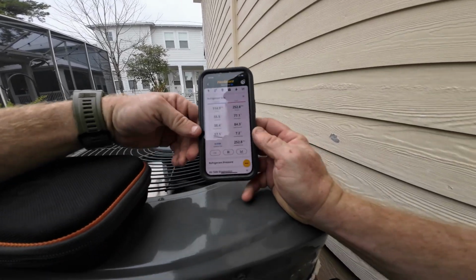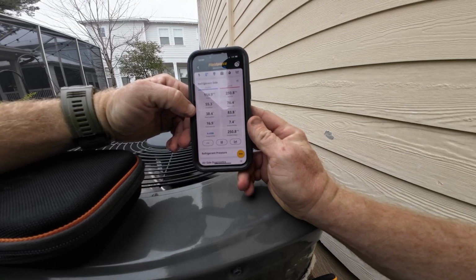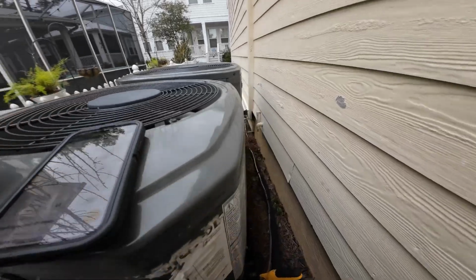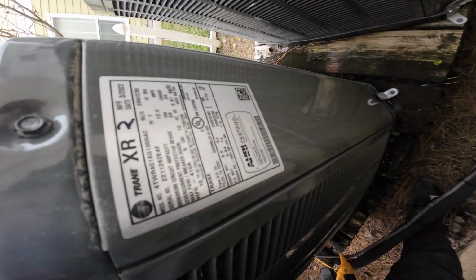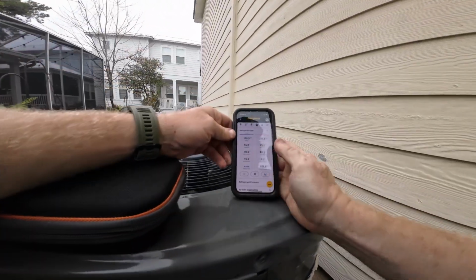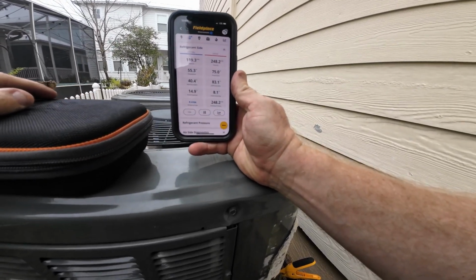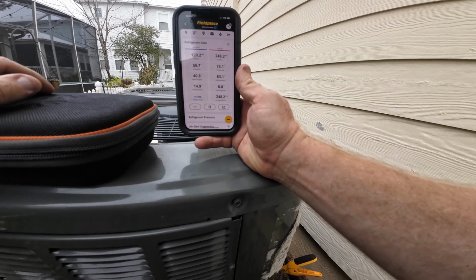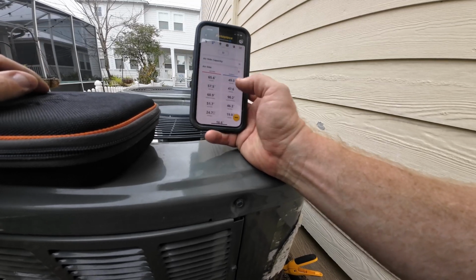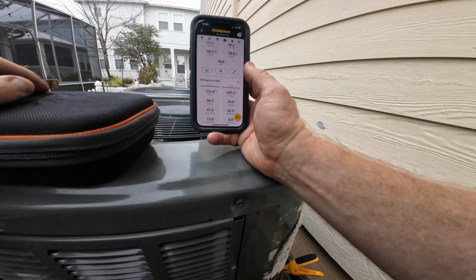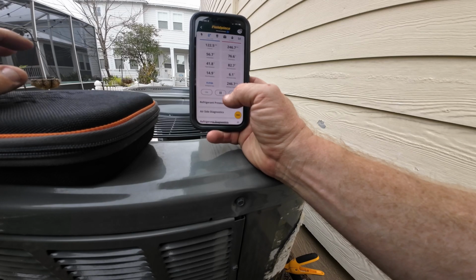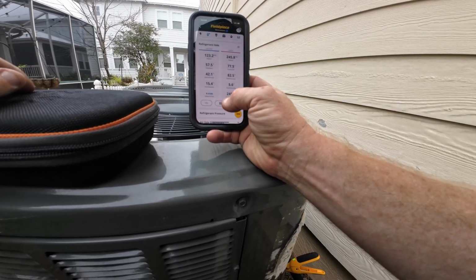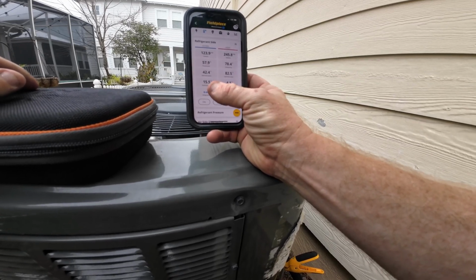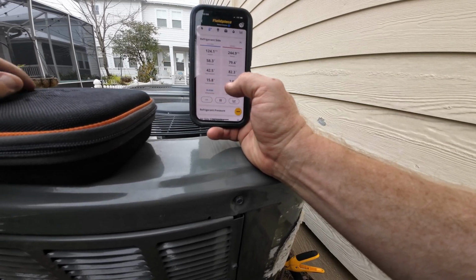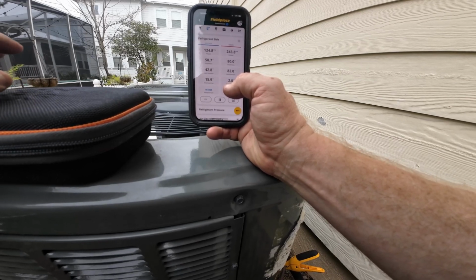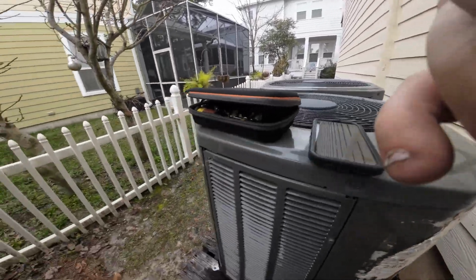Run for a little bit and see what our Supco is. See what it's asking for. It is asking for 10 degrees. And we're pretty close. It's kind of cold outside, so I wouldn't want to add any. Right there. We're at 16.6 delta. It just dropped down. It's dropping now. That's pretty low on the superheat. I might add a little bit and see what happens with the temp split.